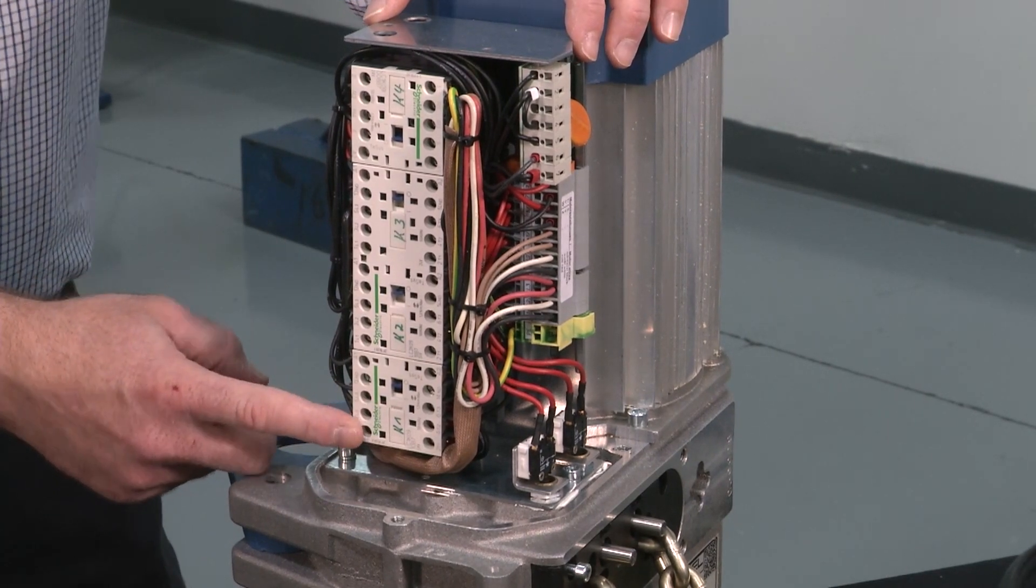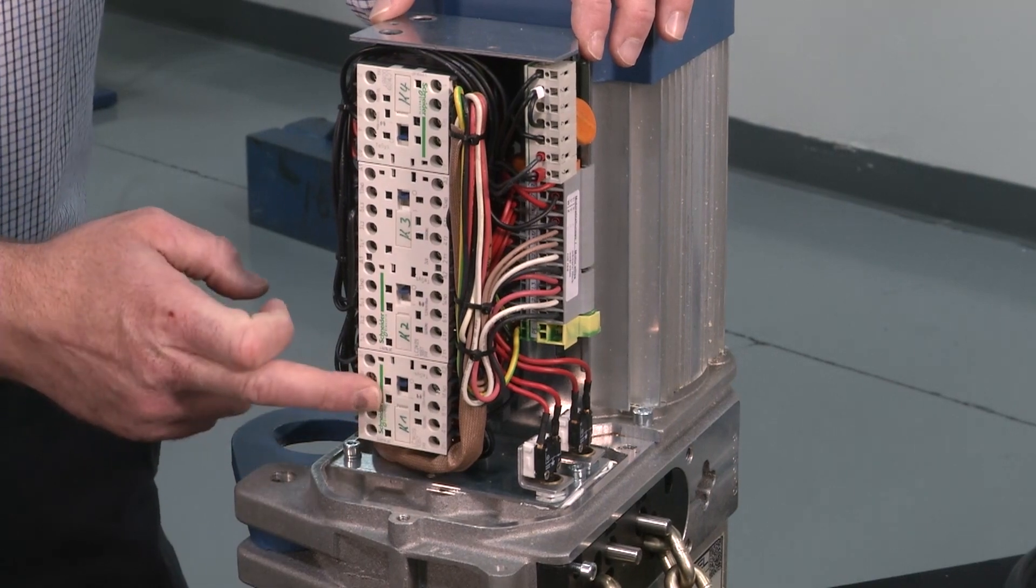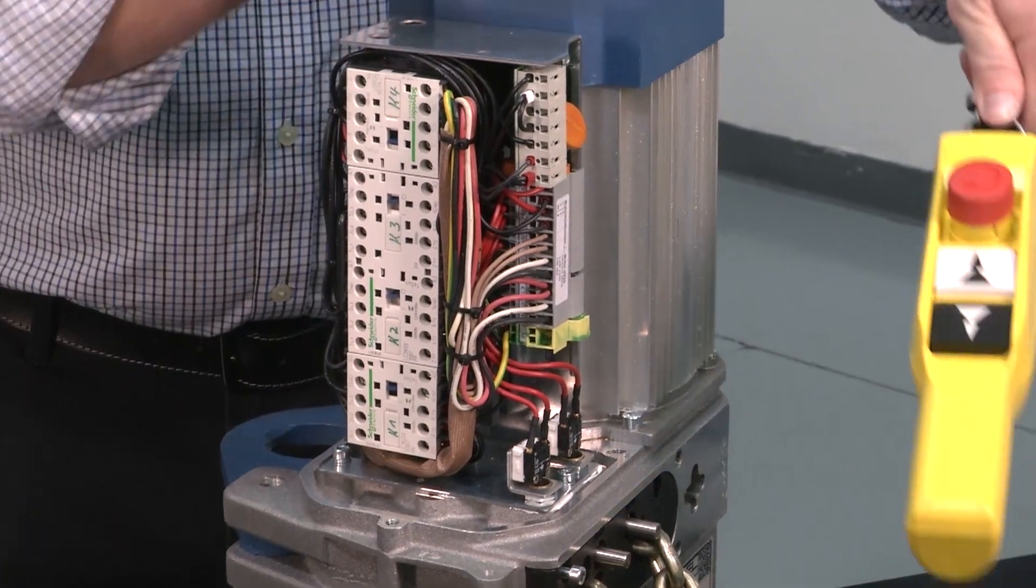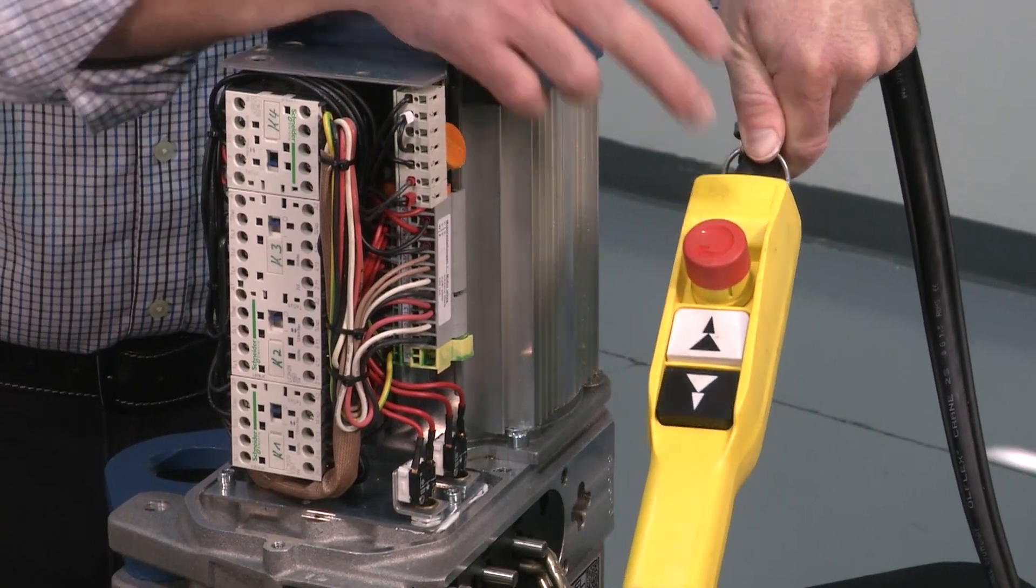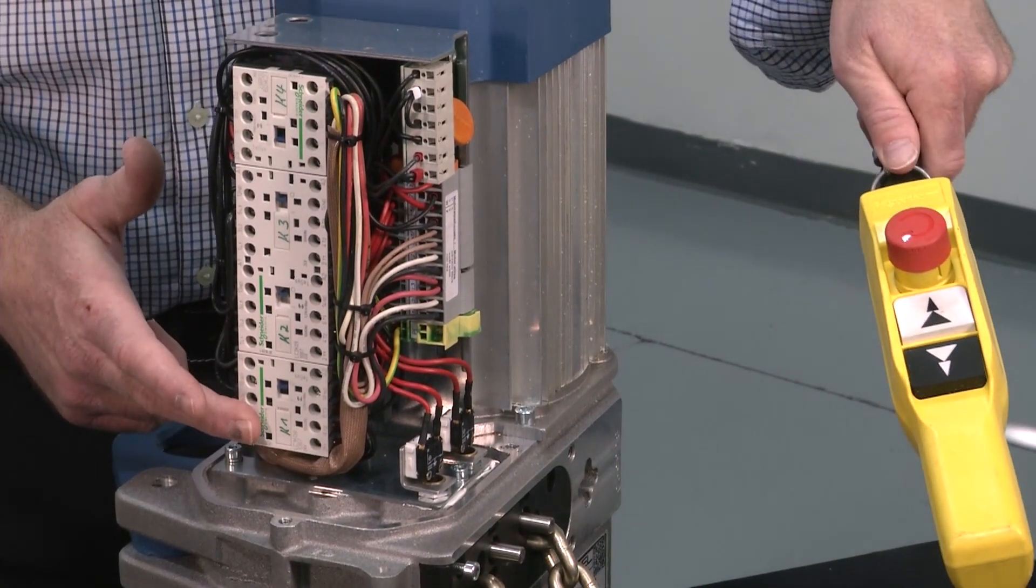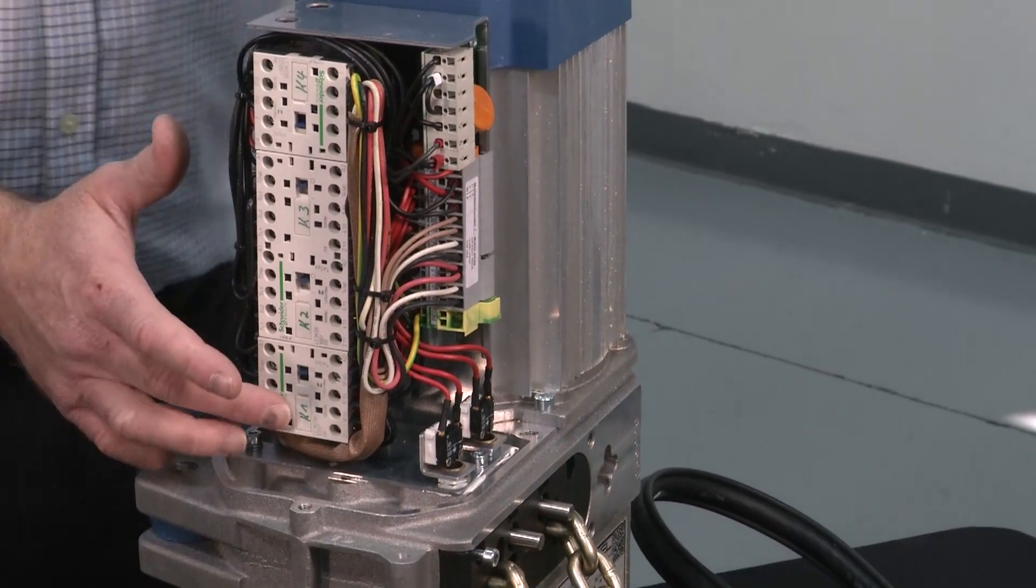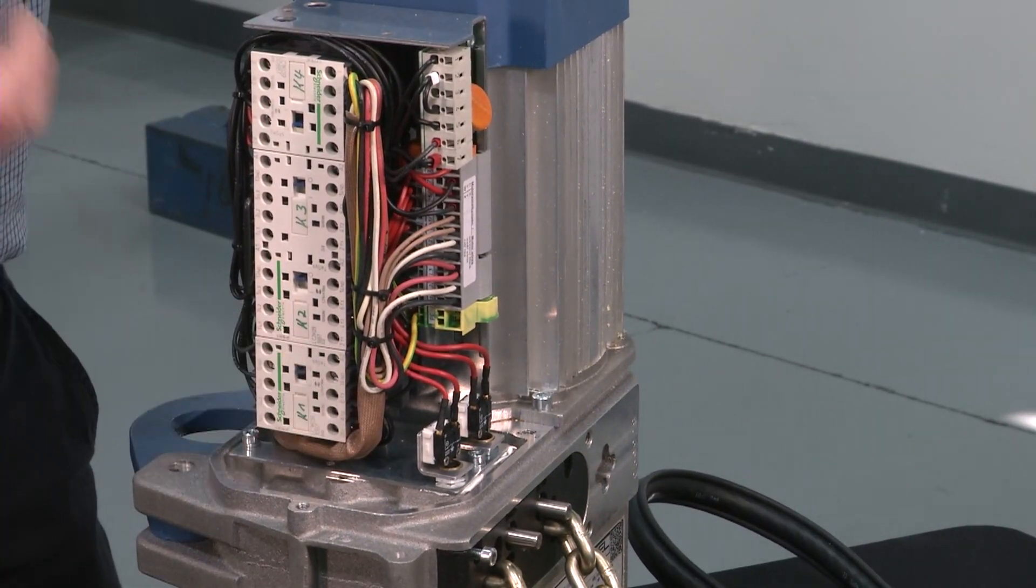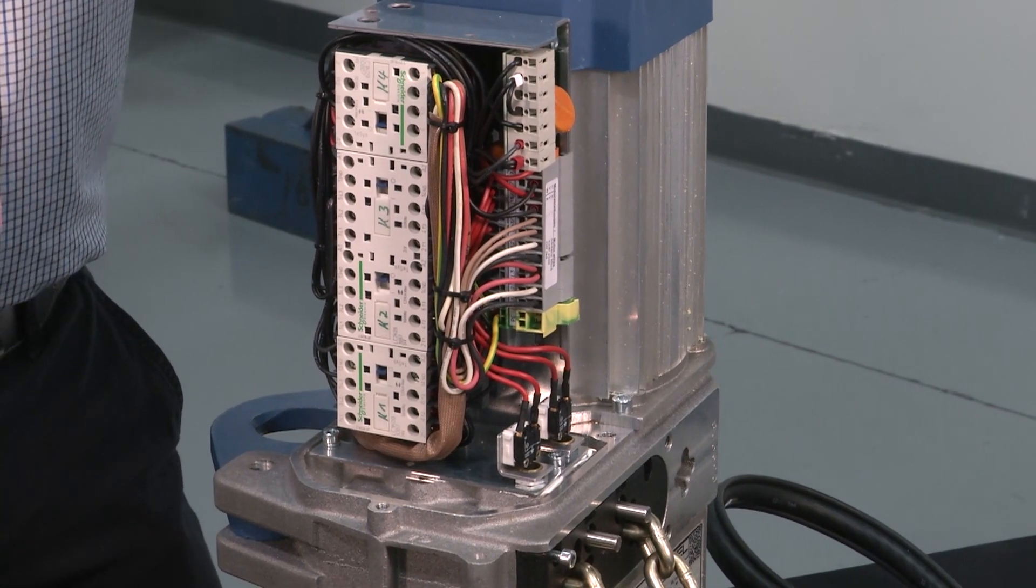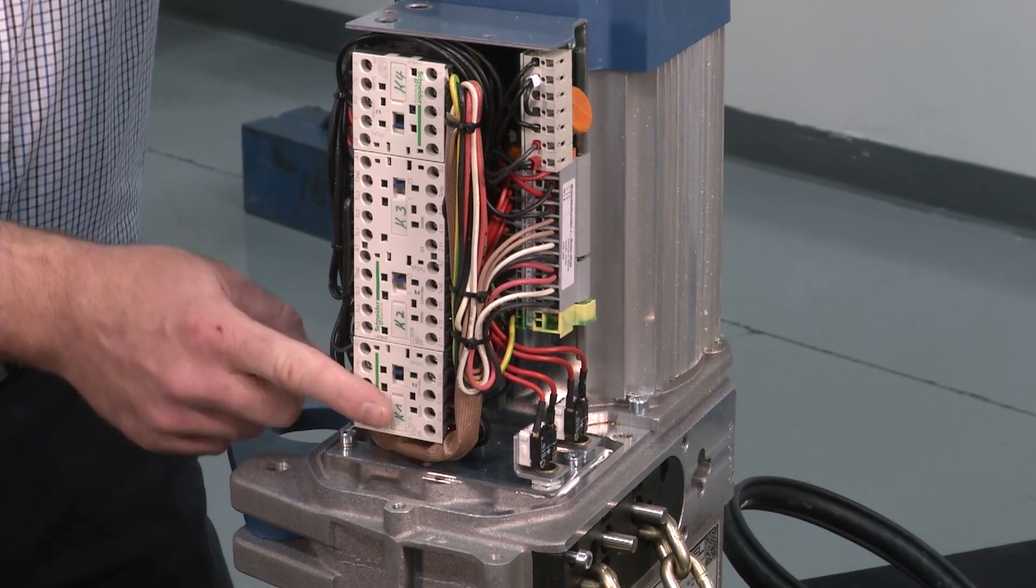So every hoist comes with an e-stop push button, and every e-stop is tied to a true mainline contactor. There are other hoists out there that don't have actual mainline contactors. Sometimes you'll see they're just simply using the e-stop to break the control line, but we're actually making and breaking an actual mainline contactor with that e-stop.